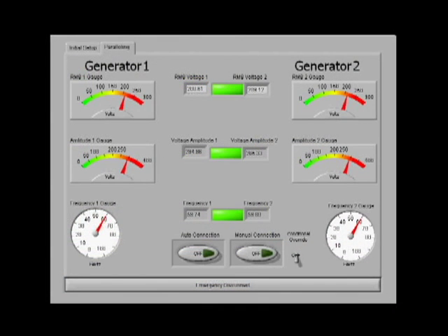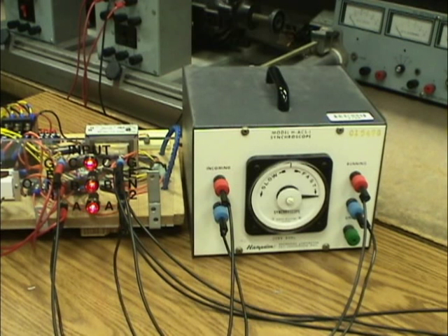LabVIEW indicates that the voltages and frequencies are matched, and then the auto connect button is pressed to begin the phase angle difference detection. The synchroscope is introduced to help visually represent that the auto connection feature works correctly. When the needle of the scope is near the 12 o'clock position, the generators will connect by closing a relay connecting the generators' outputs together.